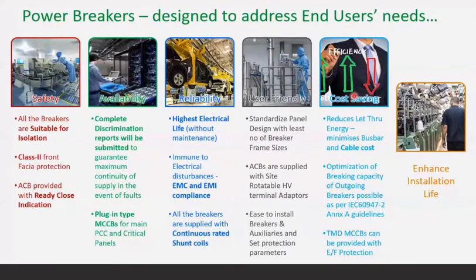So we will cover in the next slides how this cost saving will come to your side, if you look at the values Schneider switchgears are providing. So we can optimize the breaking capacity of outgoing breakers. This is in line with the guidelines of IEC 60947-2. It talks about cascading. So we have the concept called cascading.